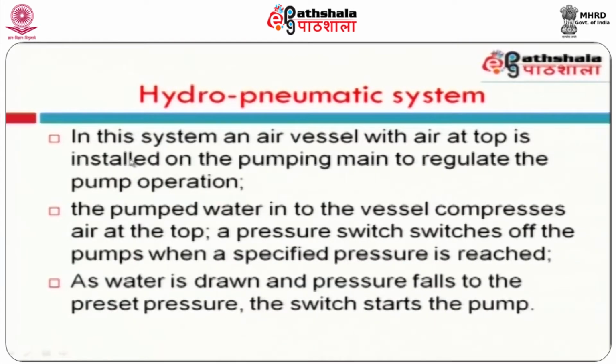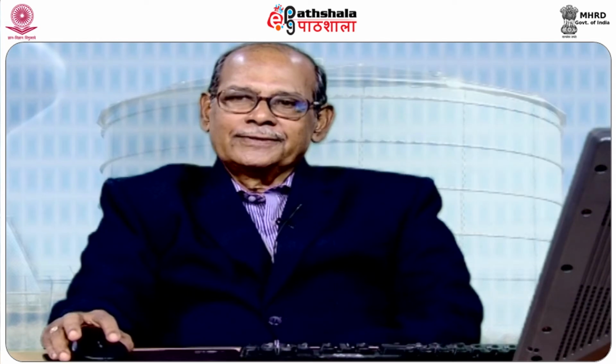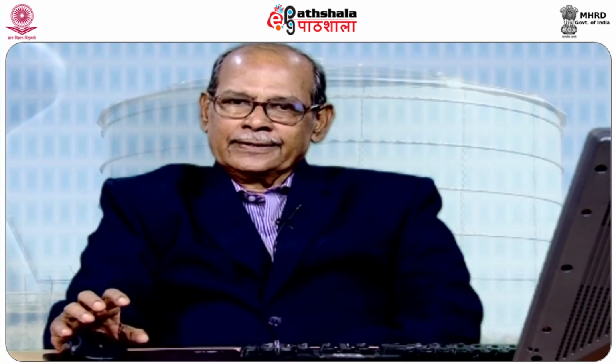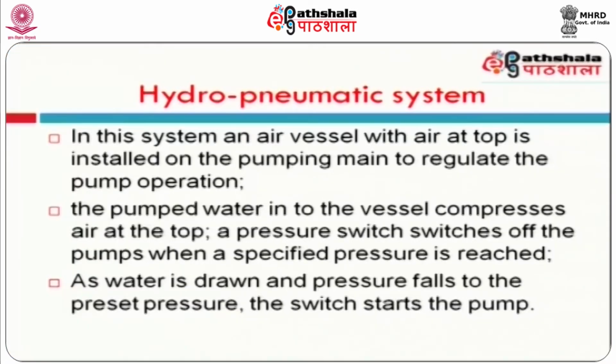That pressure tank is known as the hydro-pneumatic system, where a vessel is provided, to which the main is connected. On the top of the vessel you have an air space. So, when there is no supply, the air will be compressed and the water will be stored. The air at the top of the vessel is connected to a compressor. When the air is reduced, the compressor will provide the necessary air.